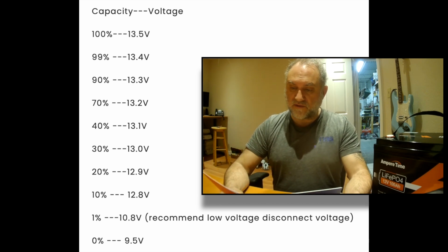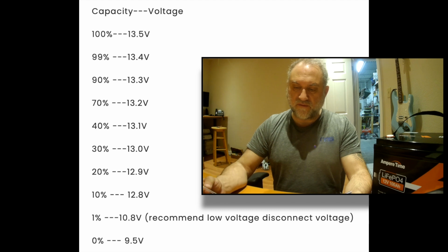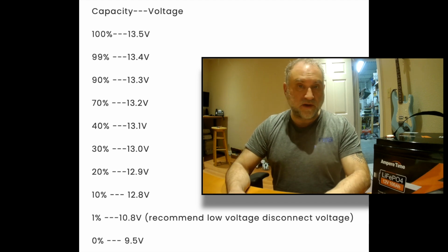That's the state of charge chart. At 13.5 volts it's 100% charged. At 13.4 it's 99%. At 13.3 it's 90%. At 13.2 it's 70% charged. At 13.1 it's 40%. At 13.0 it's 30%. At 12.9 it's 20%. And at 12.8 it's 10%.